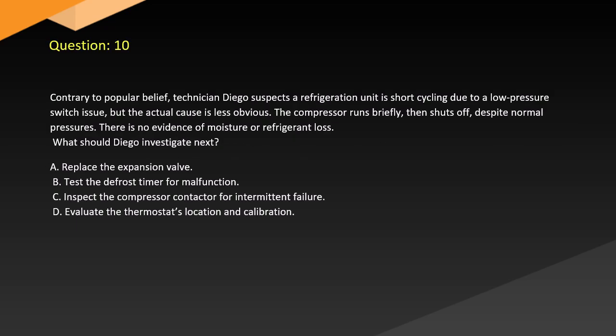Question 10. Contrary to popular belief, technician Diego suspects a refrigeration unit is short-cycling due to a low-pressure switch issue, but the actual cause is less obvious. The compressor runs briefly, then shuts off despite normal pressures. There is no evidence of moisture or refrigerant loss. What should Diego investigate next? A. Replace the expansion valve. B. Test the defrost timer for malfunction. C. Inspect the compressor contactor for intermittent failure. D. Evaluate the thermostat's location and calibration.